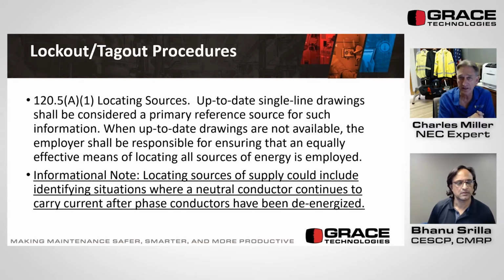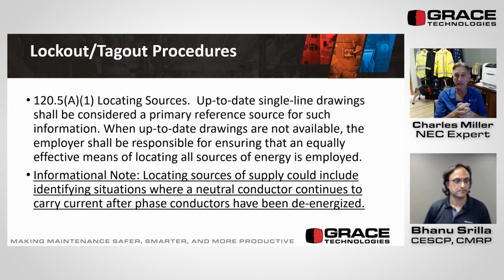There are a lot of retail facilities out there, and even industrial facilities, where rows of lights had phase A, B, C, and one neutral, but they weren't tied together. And so if someone's turning off, oh, I need circuit 22 turned off, so they turn off 22. But if circuits 24 and 26 are also energized and they use that same neutral, then there could be neutral current at a point where someone is working. So it is a good informational note to put in there to have us think about, okay, is this a multi-wire circuit, and are we turning off all the conductors or all the energy sources that use that neutral?